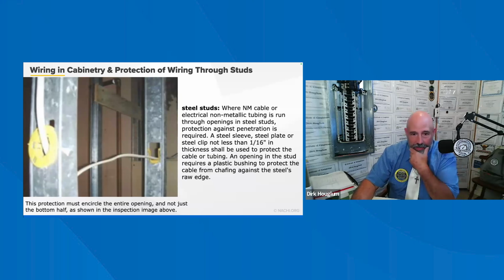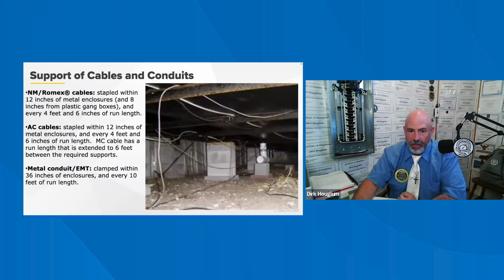I can't think the steel sleeves there. Make sure that they are protected. You've got to have protection around those wires. I see that a lot with the conduit too, using metal conduit and then having the wires just running through there. So the non-metallic Romex cables, it has to be stapled.